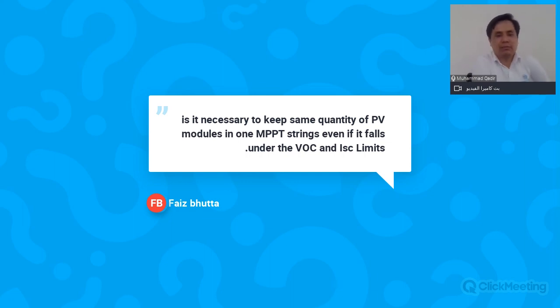Yes, it is important to have two strings going to the same MPPT with the same number of solar panels. Let's suppose you have 20 modules in string 1, then you must also have 20 modules in string 2, which is connected to the same MPPT. Why? Because these two strings might still be within the VOC and ISC limits, but they would still be affecting the output of each other.